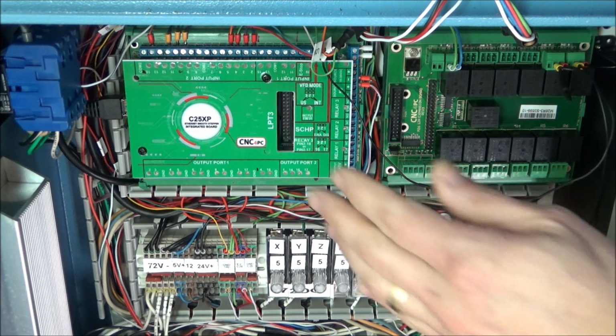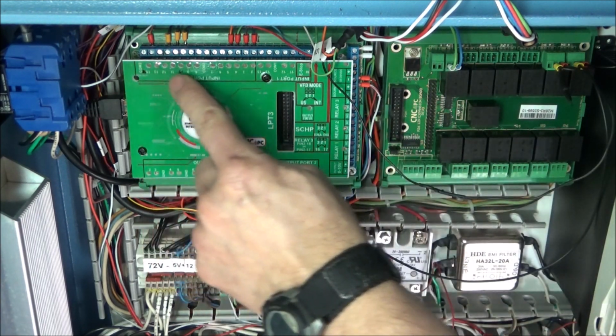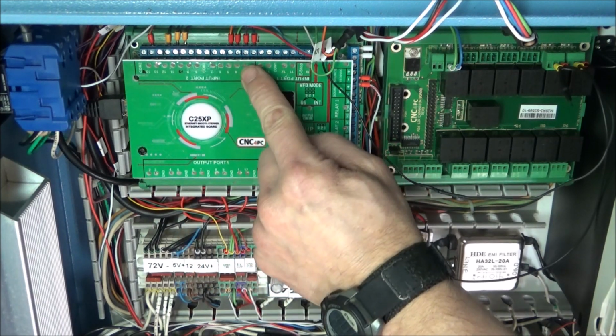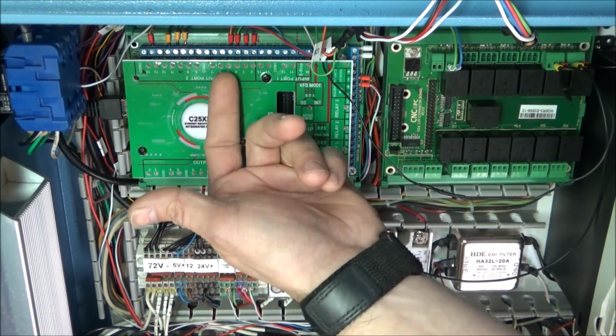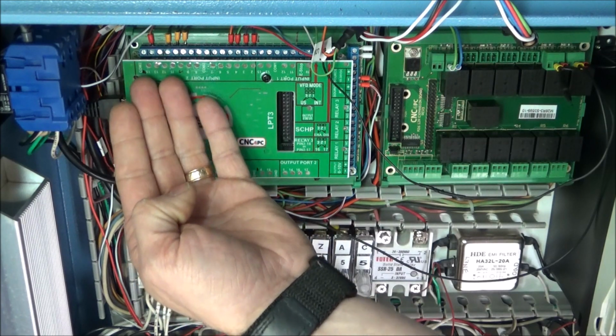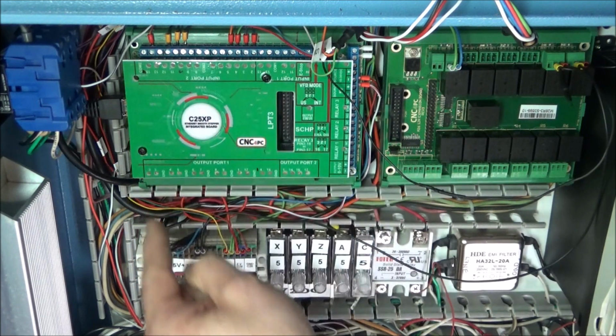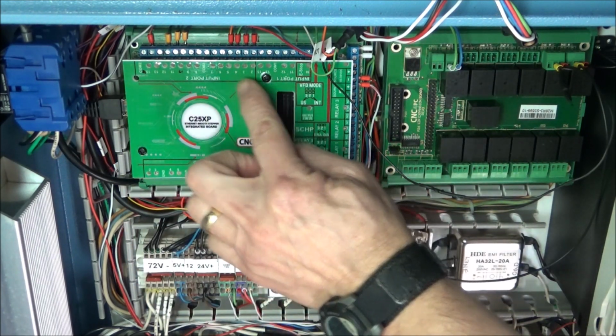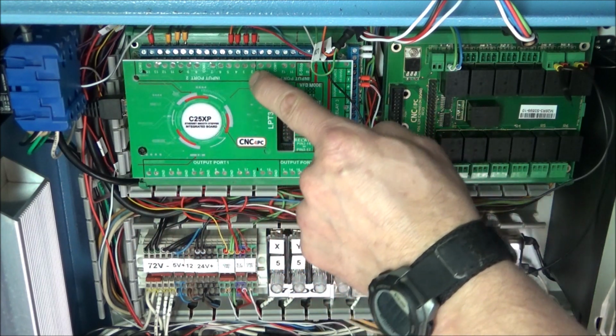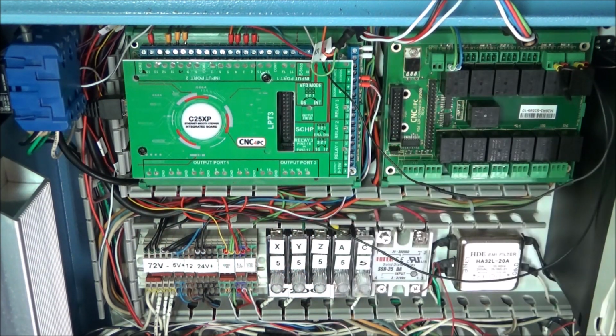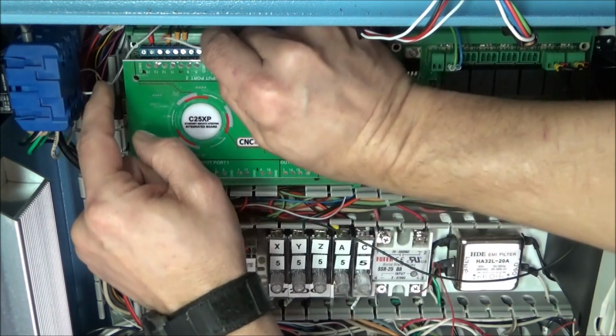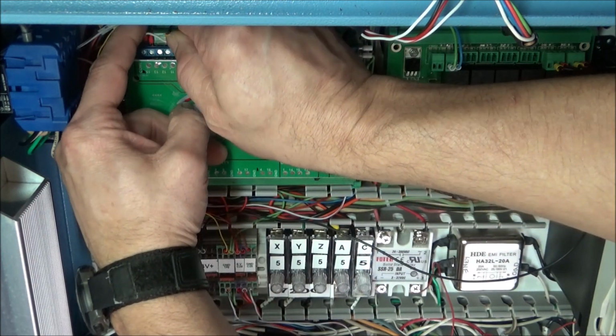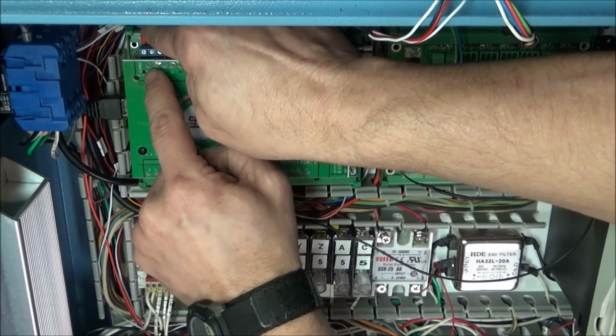Now the nice thing about the C25XP is if I were using 12 volt or 24 volt inputs, then I could do that as well. And that's why we have to land this common for whatever voltage source we're using. In my case, all of my voltage inputs are 5 volts. So I'm going to just stick this common down here.